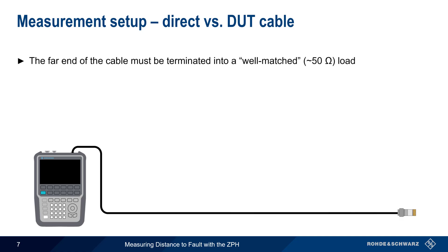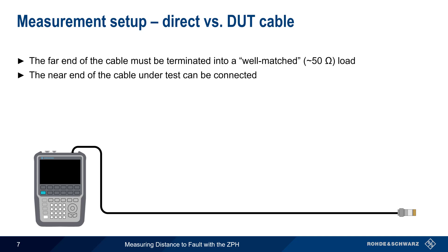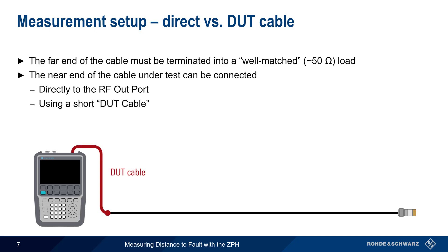To make DTF measurements, the far end of the cable under test must be terminated into a well-matched, or roughly 50-ohm load. This load may be a CAL standard, a dummy load, or an antenna that is resonant at the measurement frequency. Erroneous distance to fault measurements are often caused by a failure to terminate the far end of the cable. The near end of the cable can be connected directly to the ZPH's RF output port, or the cable can be connected using a short, high-quality DUT, or device under test cable.